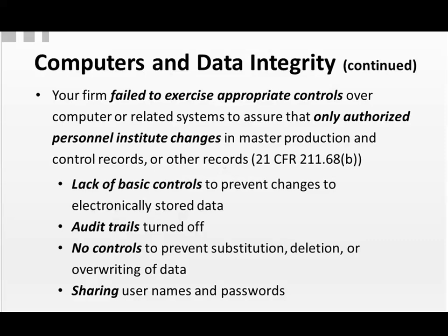In some cases, they found that there were audit trails associated with the applications, but they were turned off. No one should ever be allowed to or able to turn off or delete an audit trail. There were no controls in place to prevent the substitution, deletion, or overwriting of data. So there was no audit trail, and there was nothing to prevent someone from changing data, whether it was proper or not.